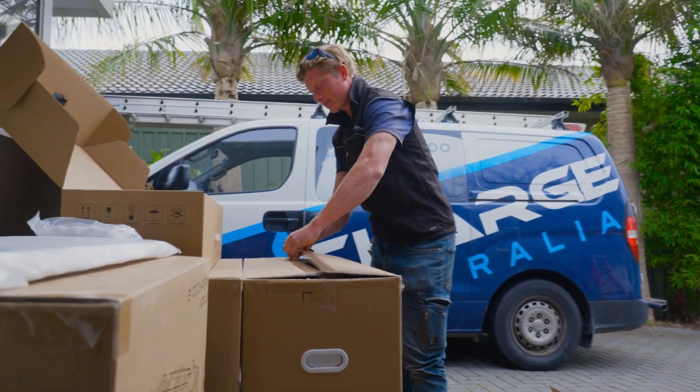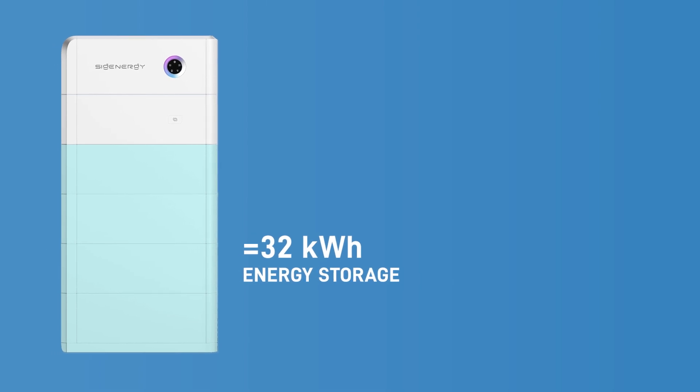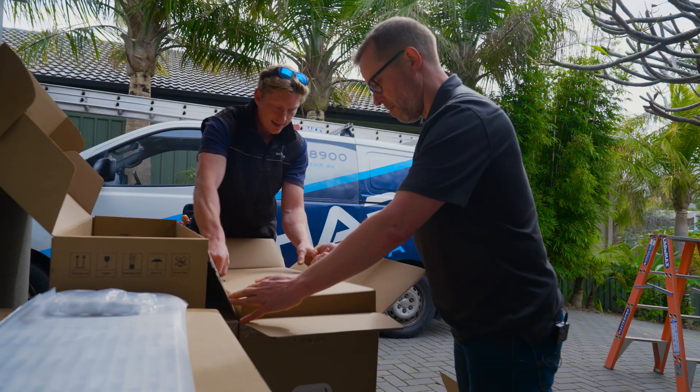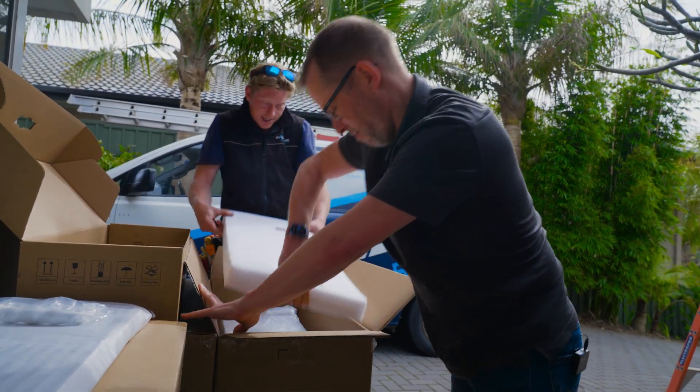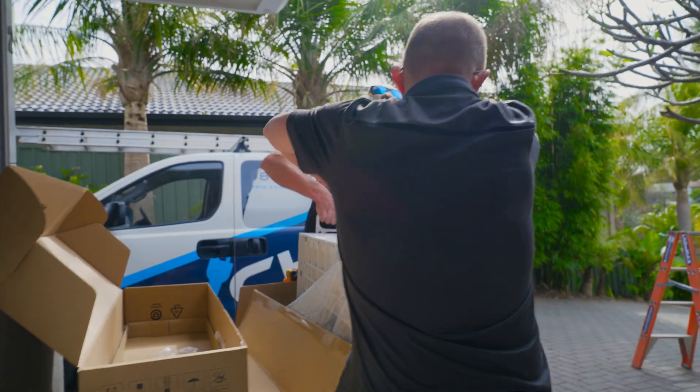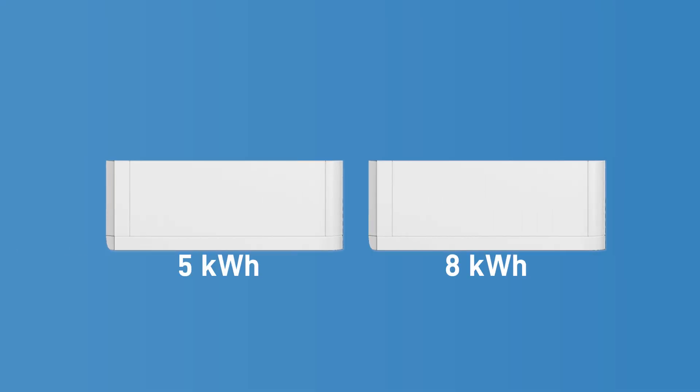These battery modules are 8 kilowatt hours of storage with 4 kilowatts of power each. So the four modules we're installing today will be 32 kilowatt hours of energy storage and a chunky 16 kilowatts power output. Sigenergy also make a 5 kilowatt hour module with 2.5 kilowatts of power, and you can mix the five and the eight in the same stack, with an 8 kilowatt hour brick costing 20% less per kilowatt hour.